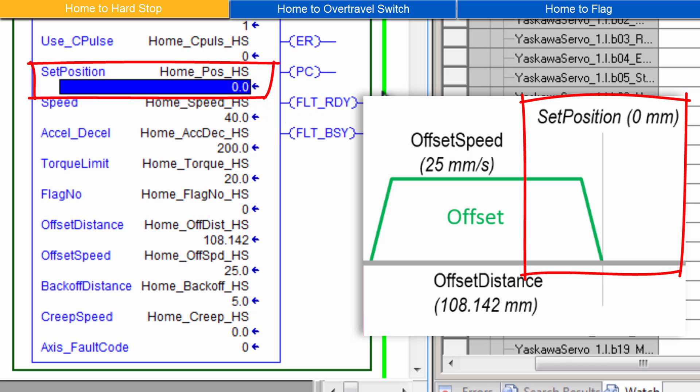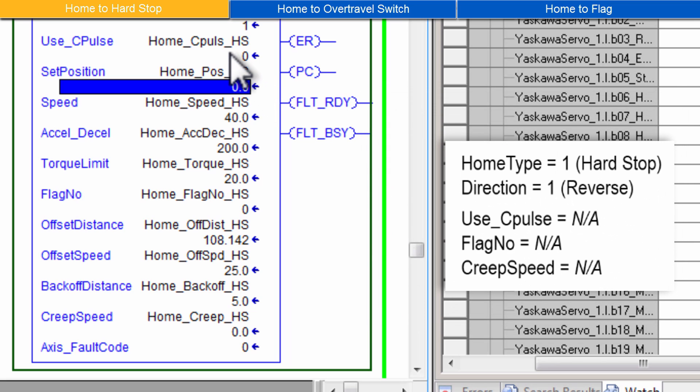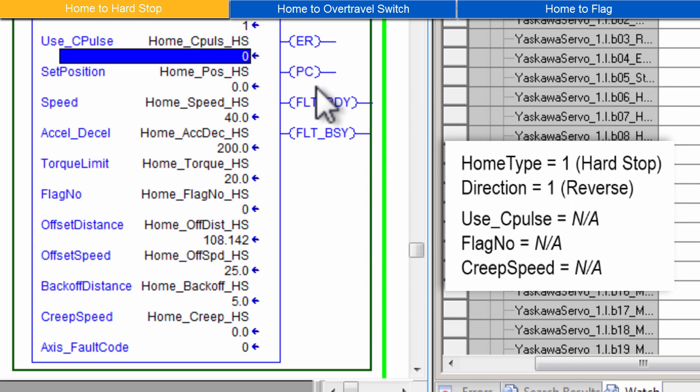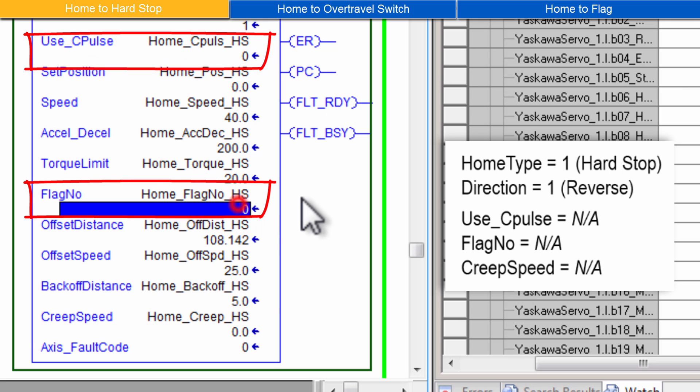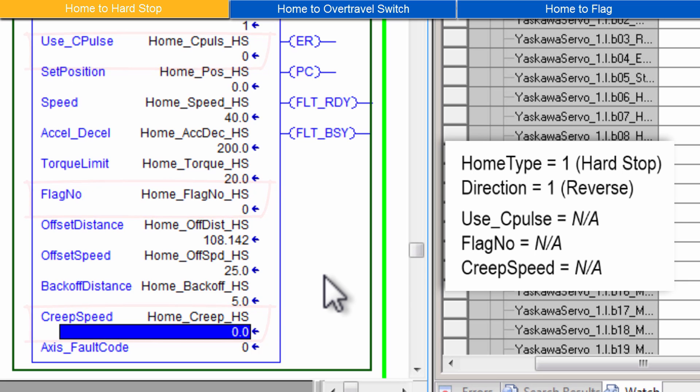Set Position will be the servo's new position after the homing sequence completes. Zero is typical. You may have noticed 3 parameters are not used by the Hard Stop homing method. They are Use C-Pulse, Flag Number and Creep Speed. The values for those parameters are ignored.